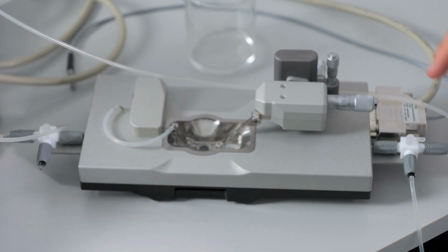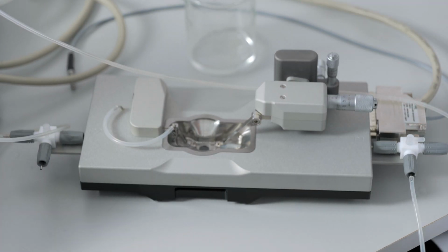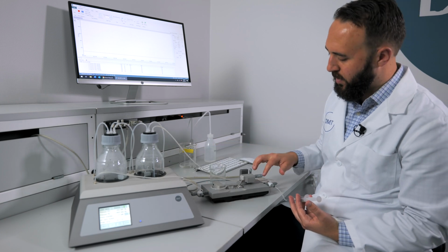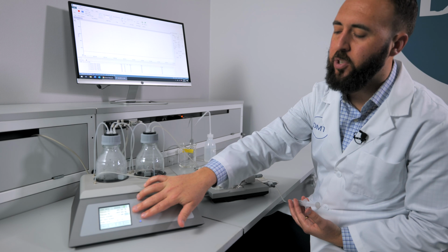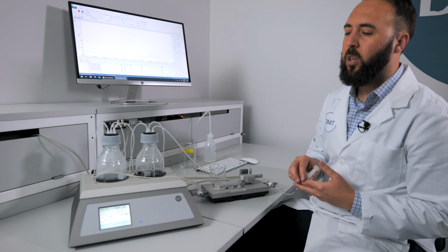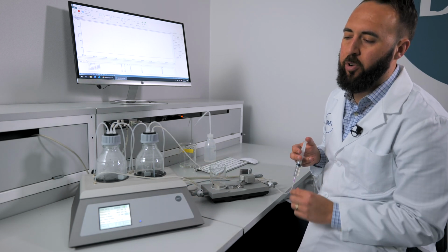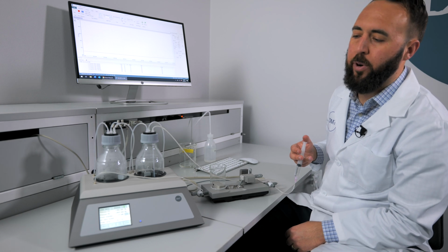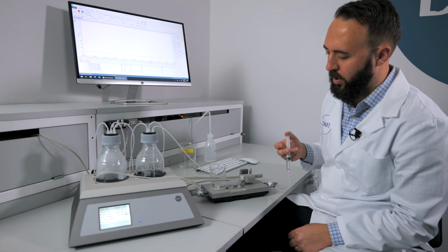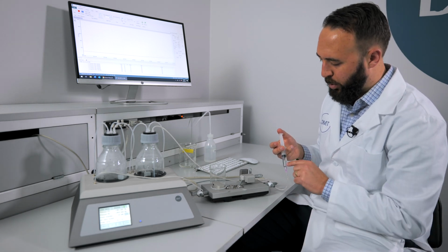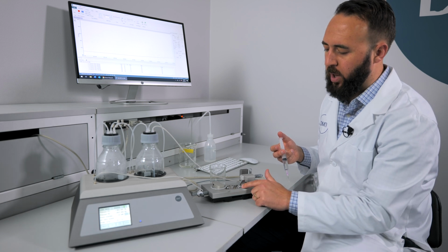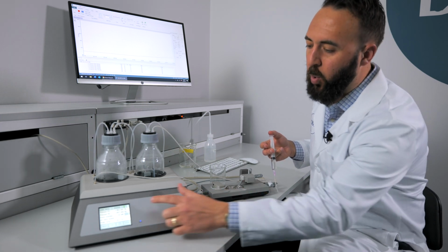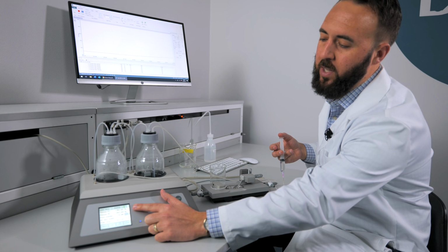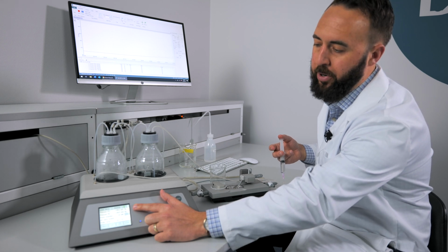When you are doing this, you need to make sure that the interface is connected to the chamber with a myograph cable, and you keep an eye on the pressures that you are adding. You can very easily exceed 200 and 250 millimeters of mercury when you're pressing with your finger. So we are now going to push some acetic acid through the lines while keeping an eye that we do not exceed 200 millimeters of mercury.